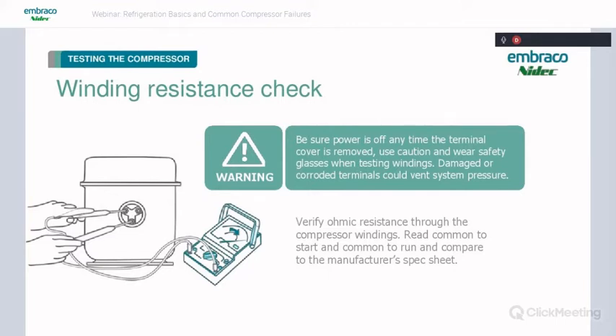And it may only be 50 or 60 PSI of pressure, but if you've ever been around this, you're going to know it's fairly violent, and it makes a pretty good pop. You don't want to have your face anywhere near that when that happens. So make sure we have the power off and wear our safety gear. And then basically we're going to verify the ohmic resistance through the compressor windings. You're just going to read common to start and common to run and compare it to the manufacturer spec sheet.